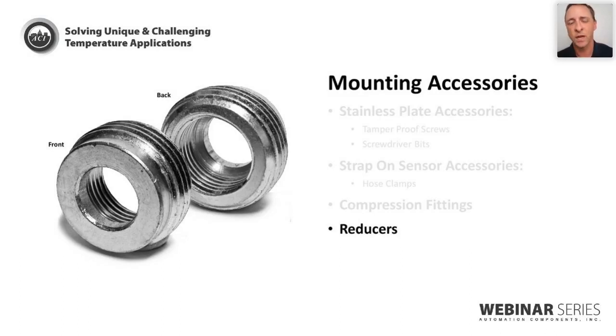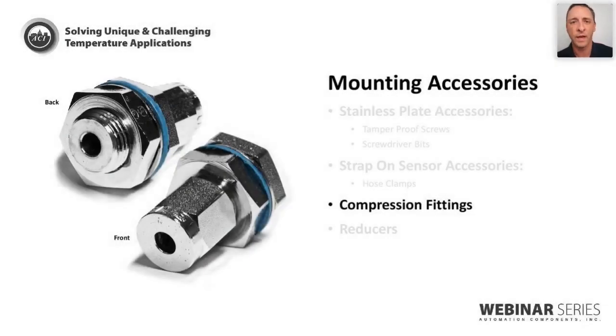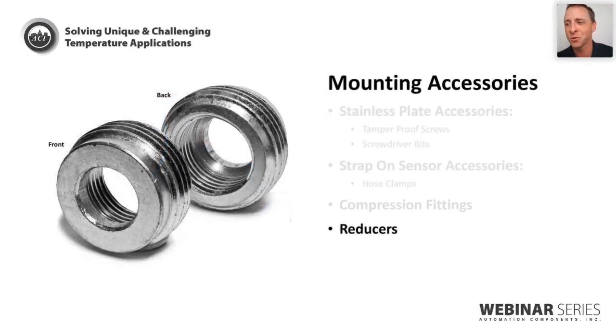For example, our standard immersion sensor fittings are 1/2-inch NPT. So these reducers allow you to install a new immersion sensor into an existing well of a different size. The compression fittings allow you to hold a probe into place where a box may not be available, or other challenging applications where you may not be able to fit a box. So these little things, they don't look like much, but they can certainly be worth their weight in gold.